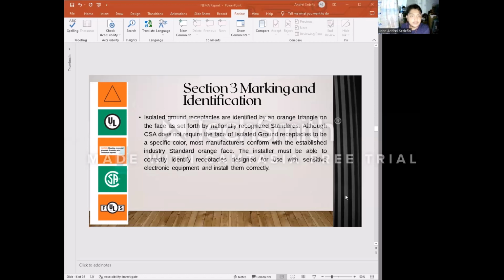Next is marking and identification. Isolated ground receptacles are identified by an orange triangle on the face, as set out by nationally recognized standard. Although CSA does not require the face of isolated ground receptacles to be a specific color, most manufacturers conform to the established industry standard orange face. The installer must be able to correctly identify receptacles designed for use with sensitive electronic equipment and install them correctly.